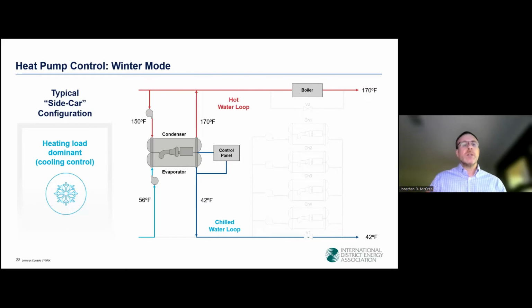So our heat pump has been sized to comfortably unload and handle all of the wintertime chilled water load in the system. So its pump is flowing all of the return chilled water through the heat pump's evaporator, and the heat pump's onboard controls are keeping the chilled water at a leaving temperature of 42 degrees desired by the system. On the hot water side, the heat pump's dedicated pump is flowing 150-degree return hot water through the heat pump's condenser, and it's producing approximately 170-degree hot water. And that water is then getting mixed in with the remainder of the return hot water and sent down the line to the boiler plant, where the boilers are taking it the remainder of the way up to the 170 that's needed in the system loop.